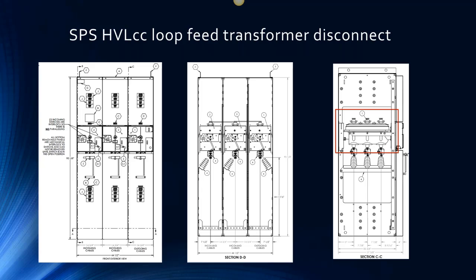Additionally, you want to be able to loop through a de-energized transformer. If you need to work on the 480 volt side of that transformer, you can turn off the switch that feeds the transformer while keeping the other 2 on, and that will enable you to continue, you have continuity in your loop, and then you can work on the 480 volt side of that transformer and ensure that the transformer is dead via the visible disconnect available in this switch.